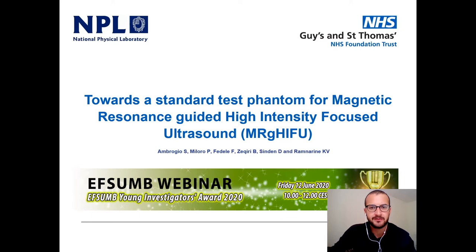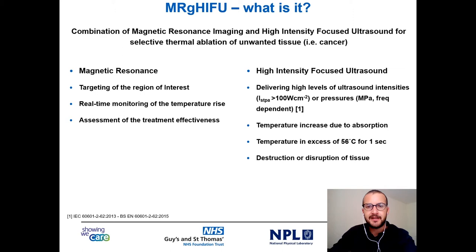MR-guided HIFU is the combination of magnetic resonance imaging and high-intensity focused ultrasound for thermal ablation of unwanted tissue. An HIFU transducer delivers a high level of ultrasound intensities to increase the temperature in the tissue. When the temperature exceeds 56 degrees for one second, there is irreversible damage of the tissue. Magnetic resonance imaging is used for targeting the region of interest, for monitoring the temperature in real time, and for assessing treatment effectiveness.